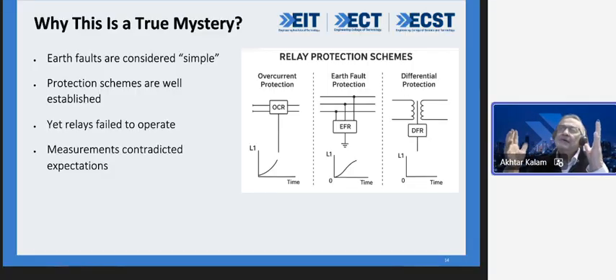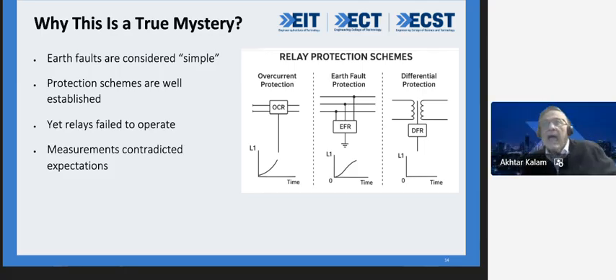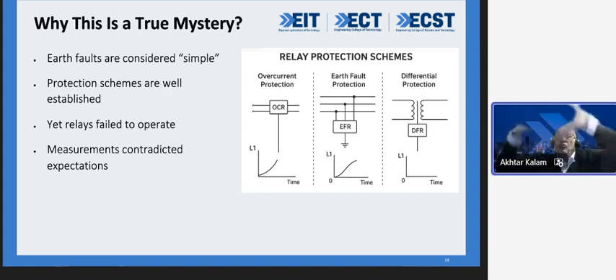And if you ask any engineering person, anyone, even a technician, the earth fault, they say, is a very simple matter. We all know, and if you don't know, please know from now, the protection schemes for any such type of faults or abnormalities in the system are very well established. So there's nothing wrong, right? The scheme is established, relays are there, measurements can be done, but still the relays fail. And the measurement that came out is not what I expected. And that is a fault.